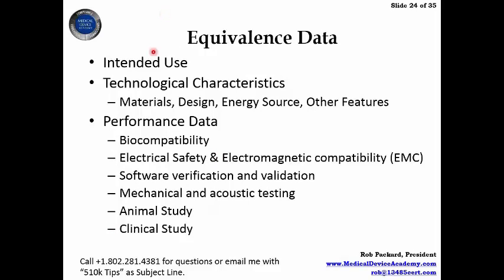Here's another thing you have to keep in mind. When you submit this equivalence data for Section 12, you need the intended use, the technological characteristics, all four of these things, and then the performance data. You're not going to actually put the data here. You're just going to tell the person where the information is. The intended use is found in Section 4. The technological characteristics are found in Section 10 under device description. Biocompatibility is found in whatever section that is. I think it's like 12. And then we have electrical safety. That's probably 17, and this might be 14 or 16. So there are a bunch of different sections. I think this right here is sections 18, 19, and 20 of the submission. So you have your different sections, and you're going to list the actual documents that have each of those pieces of information in this summary section, which is the substantial equivalence section 12.